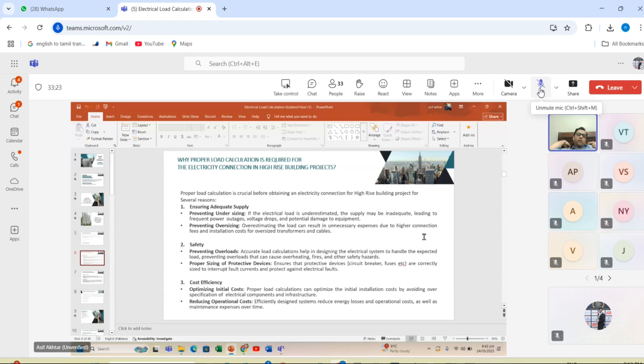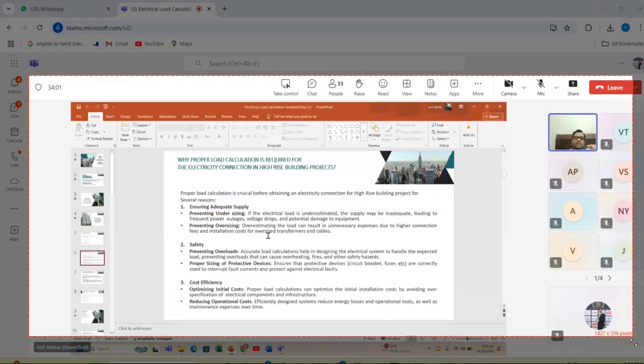The main reason for proper load calculation is to prevent undersizing and prevent oversizing. Then the second point is safety. An accurate load calculation helps in designing the electrical system to handle the expected load and prevent overloads that can cause overheating, fires, and other safety hazards. So safety is also a reason for proper load calculation and proper sizing of protection devices, meaning you have to select the circuit breakers and fuses correctly to interrupt fault currents and protect against electrical faults. Hope this point is also clear.